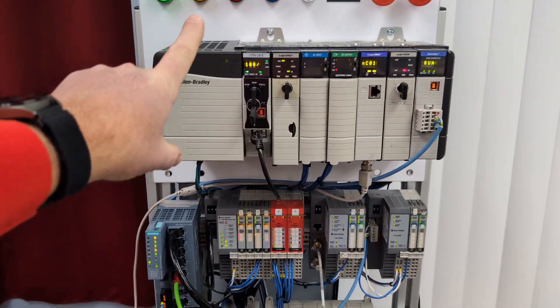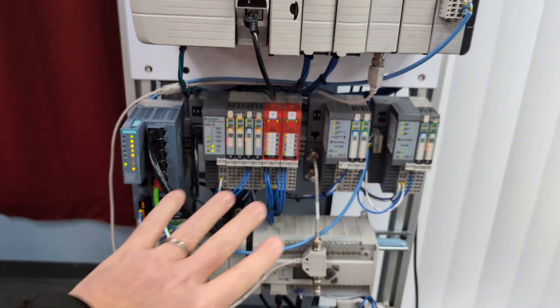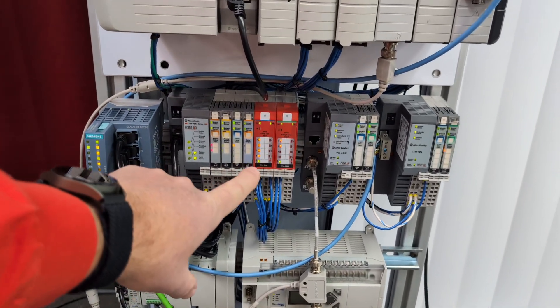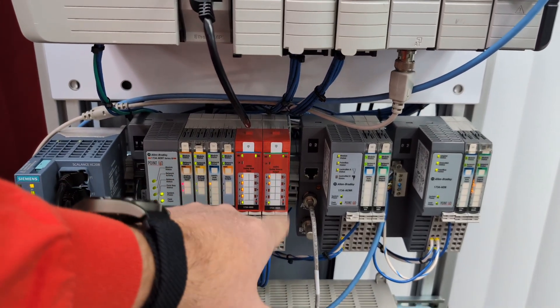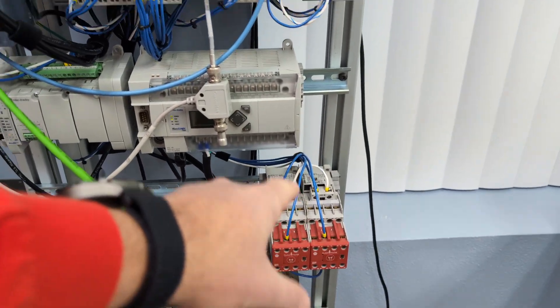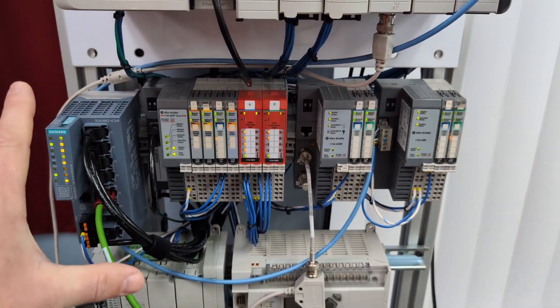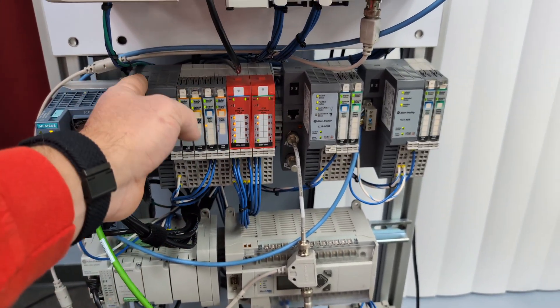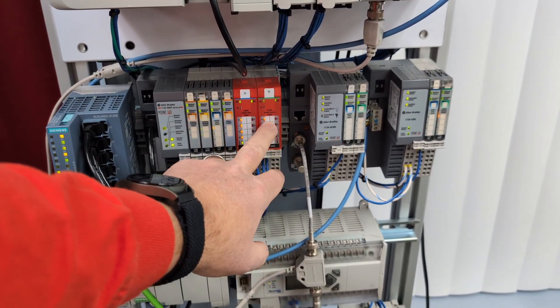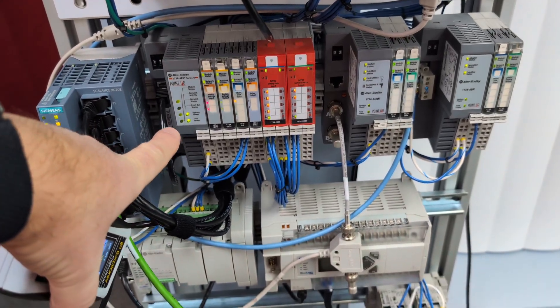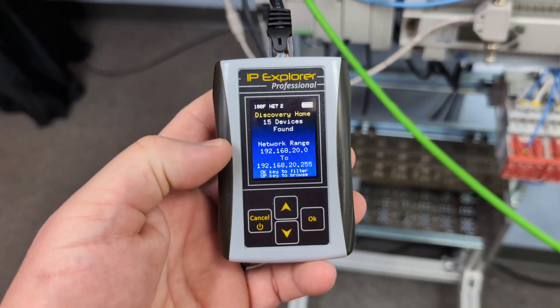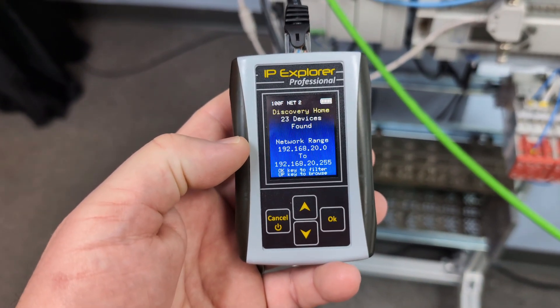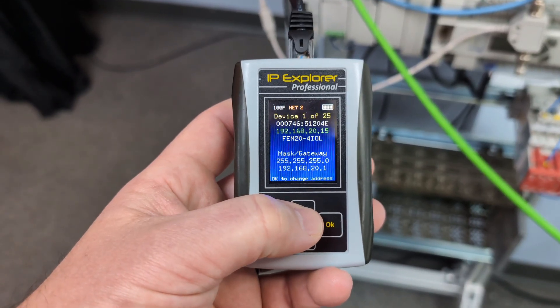This is one of our trainers. And part of this exercise is you have to find these points out on your PLC. I've got an output module here and I know that this contactor down here is controlled by this output module. Now, being unfamiliar with this, I have no idea what you may have named this output module or what you may have aliased this point. So from a troubleshooting perspective, the next thing I need is this IP address.